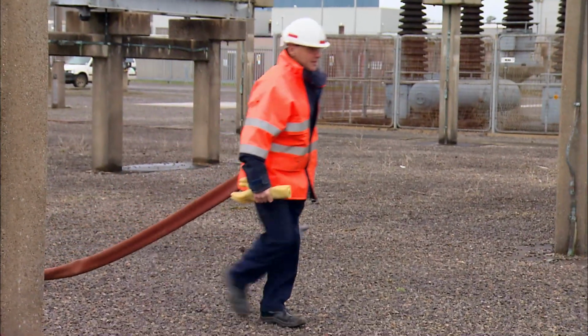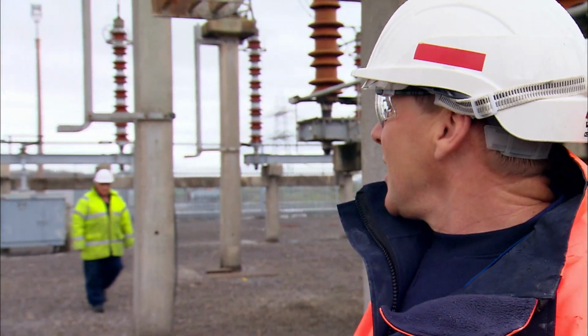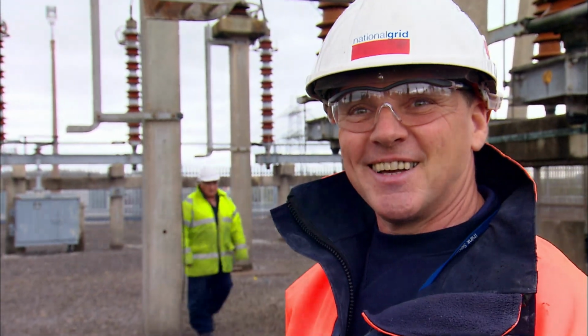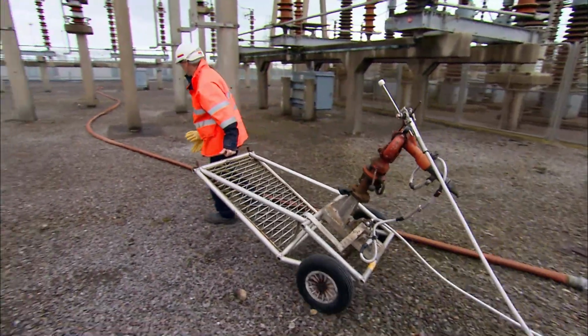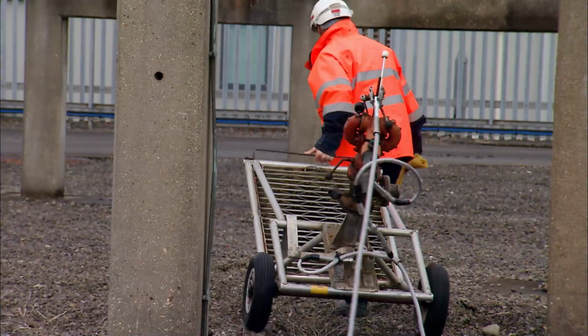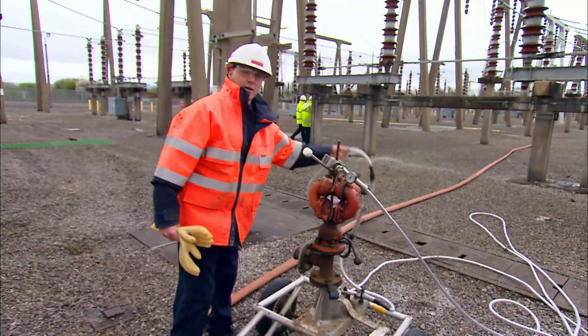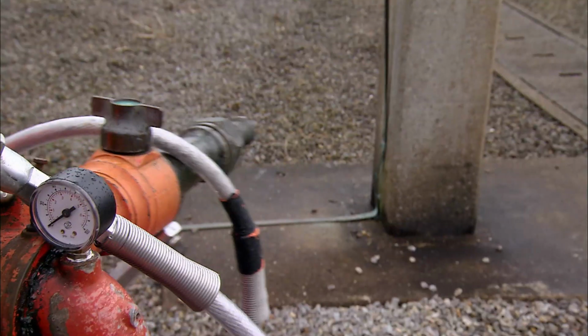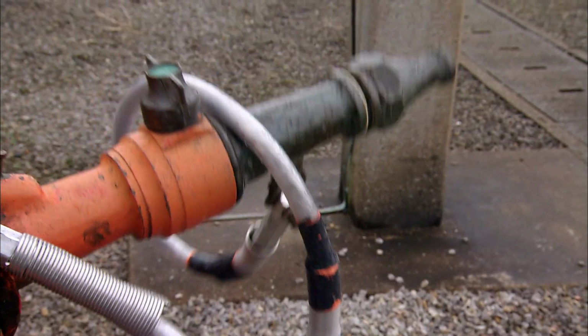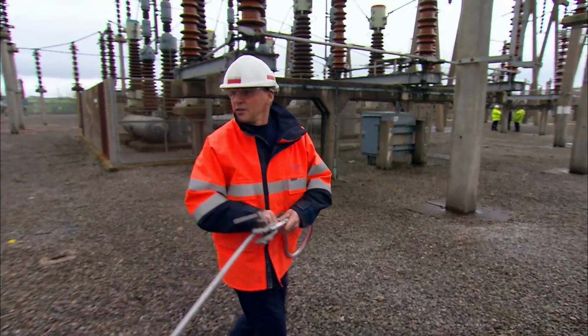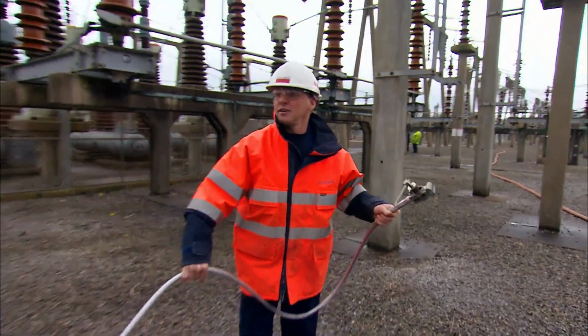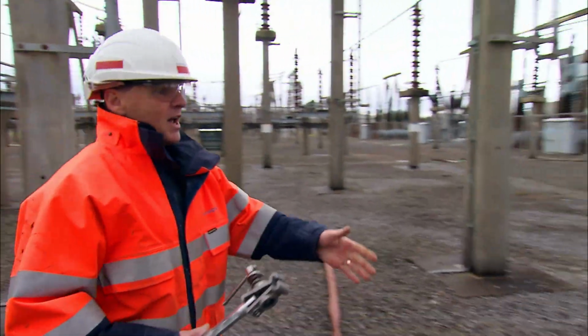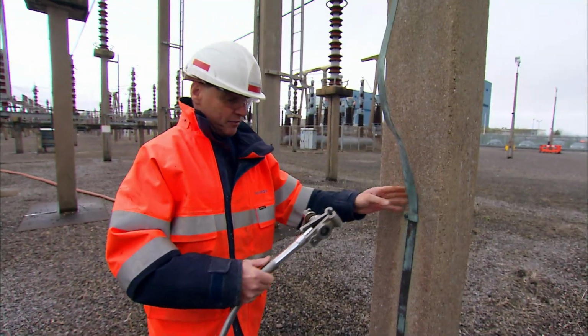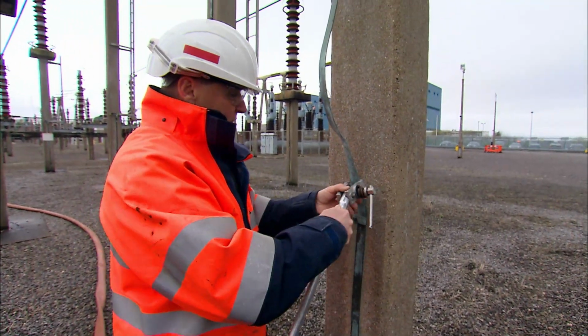The man at the sharp end is Pete. Yeah, it's going to be coming out at about 80 pounds per square inch on the 275,000 volts. As he washes, Pete will stand on an earthed platform. You've got the earth cable going under the earth. The jet comes out the front. This is just applying the earth now, which goes from the monitor, and it goes on one of these strips that we've got going down for the entire substation. So that just clamps on.